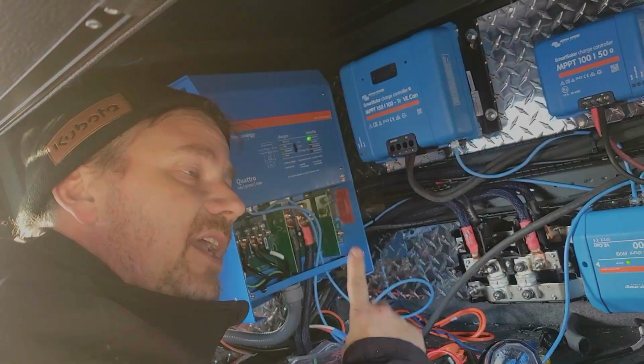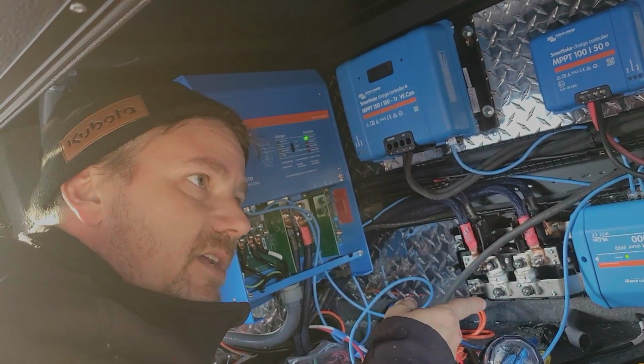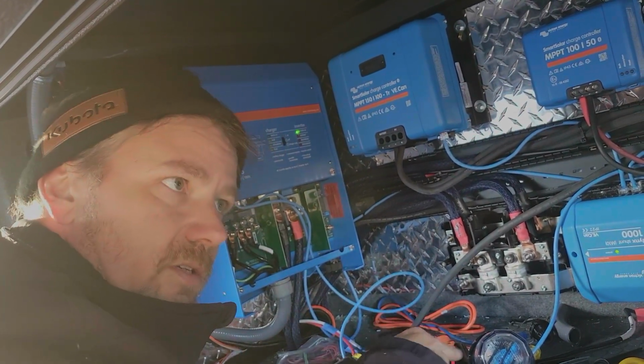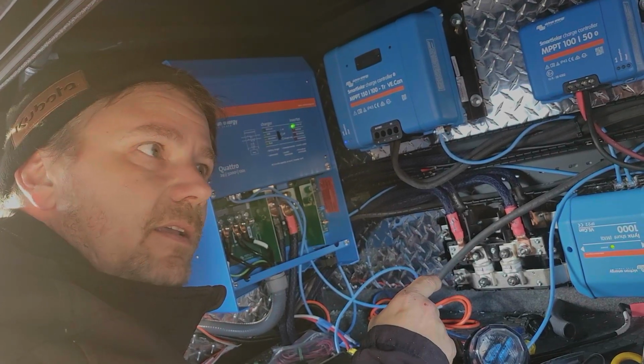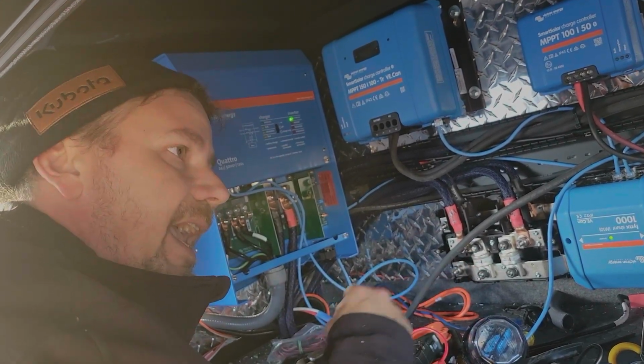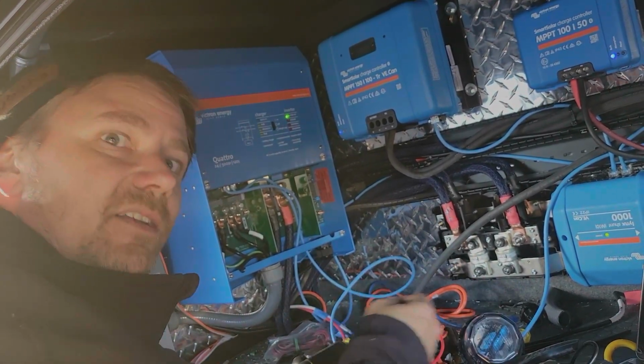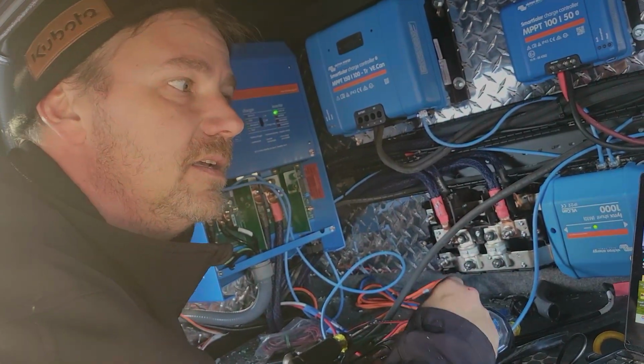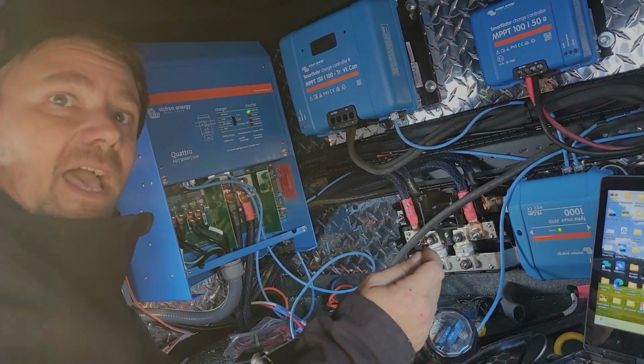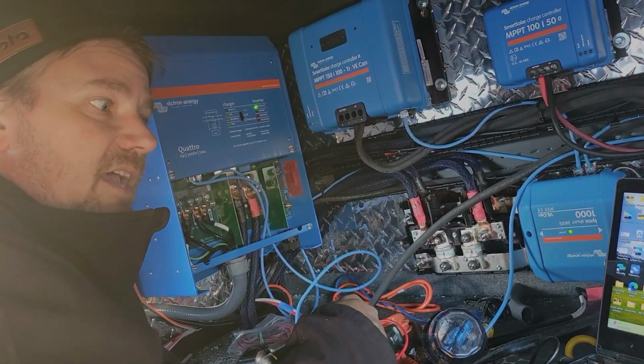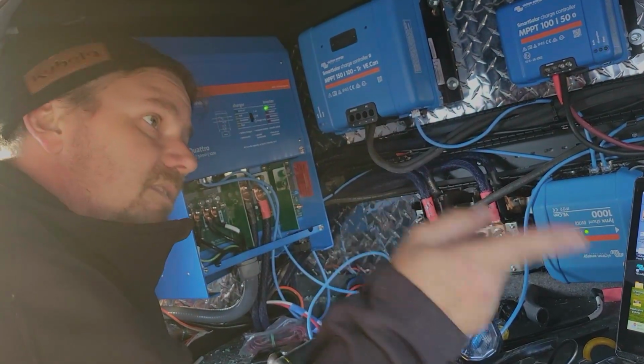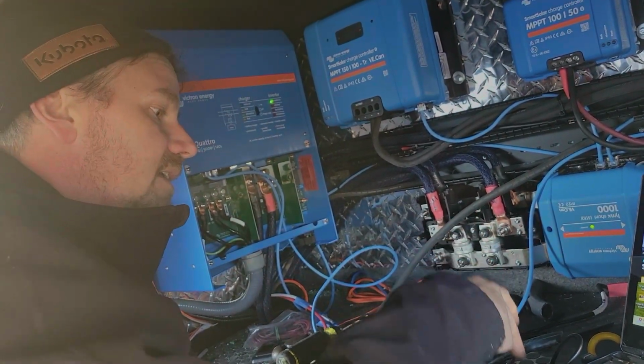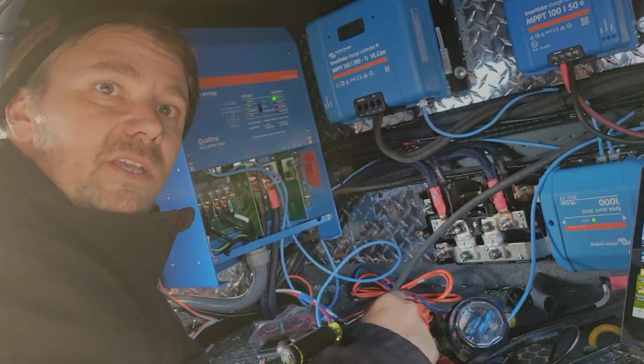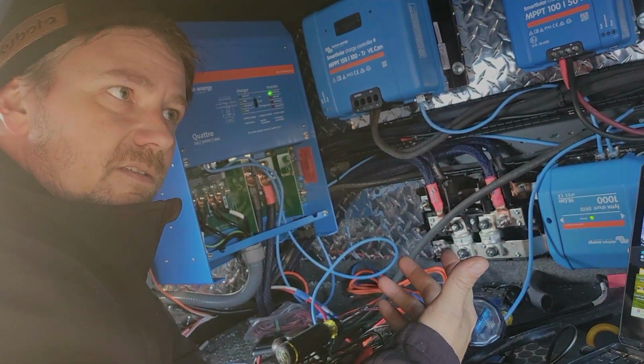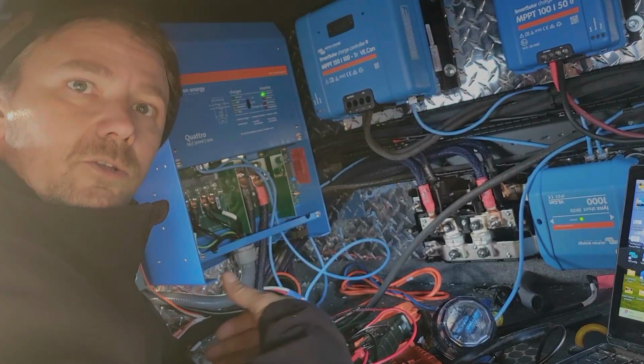Because if we have a fault somewhere in this vehicle and there is a short going to earth on the AC side, for whatever reason, it has to follow the effective fault current path, and we need it to have both paths. So it's going to have the neutral path, but if that path is broken, then it can take the ground path, and it can dissipate through the frame of the vehicle and provide a path of least resistance to prevent electric shock to a human.